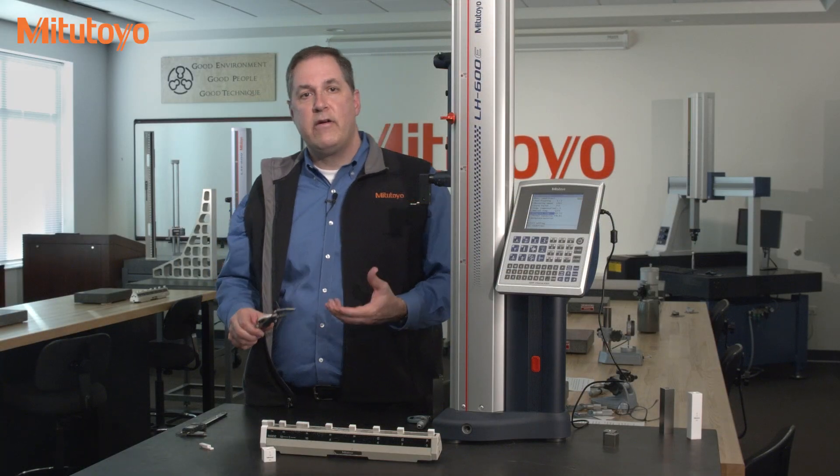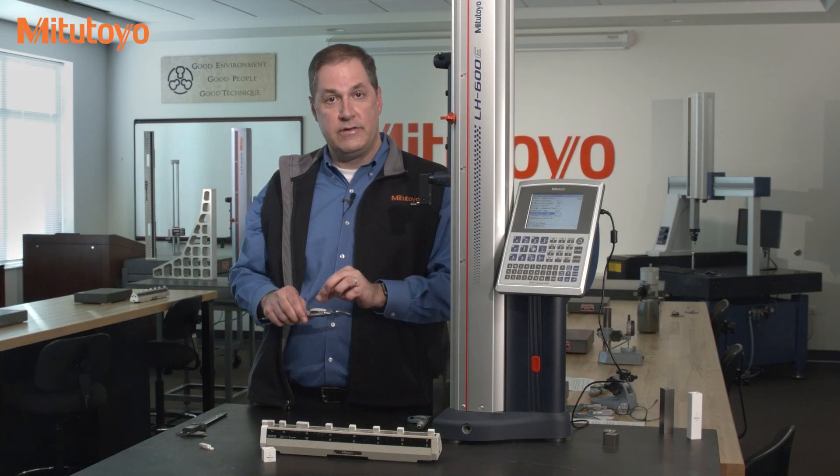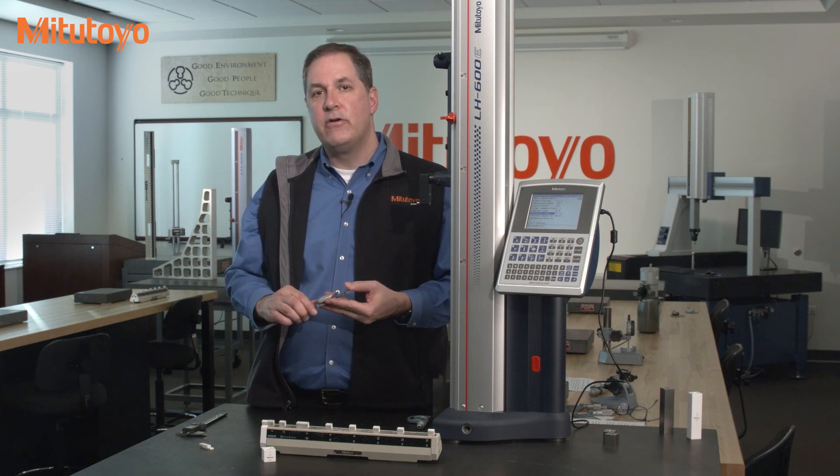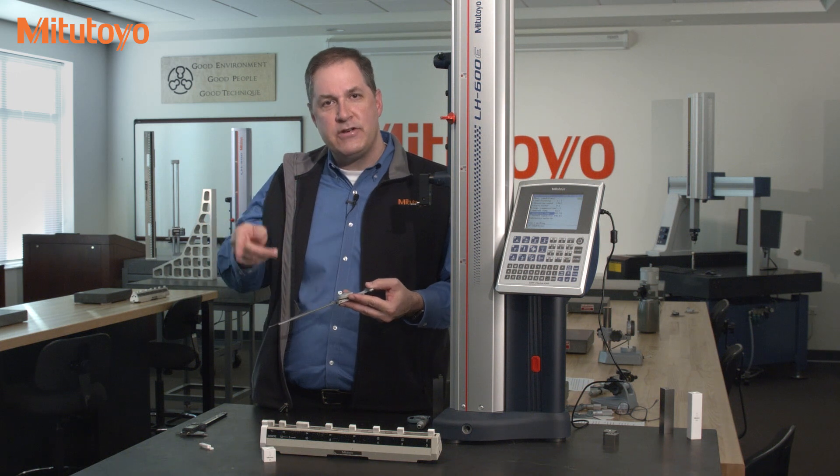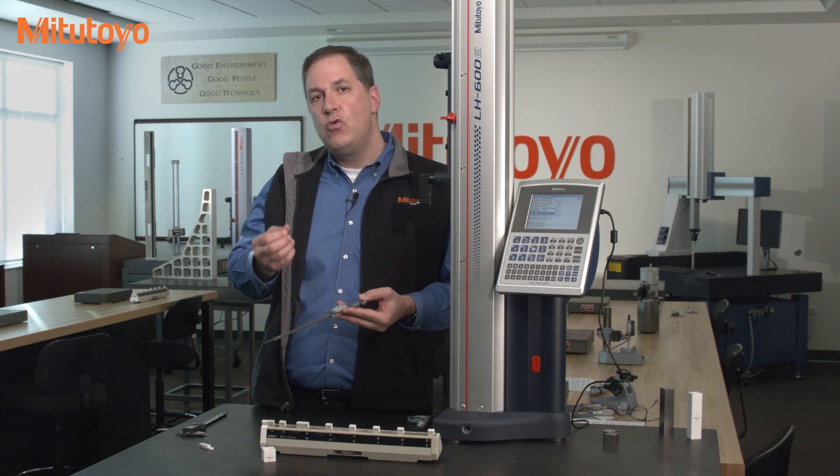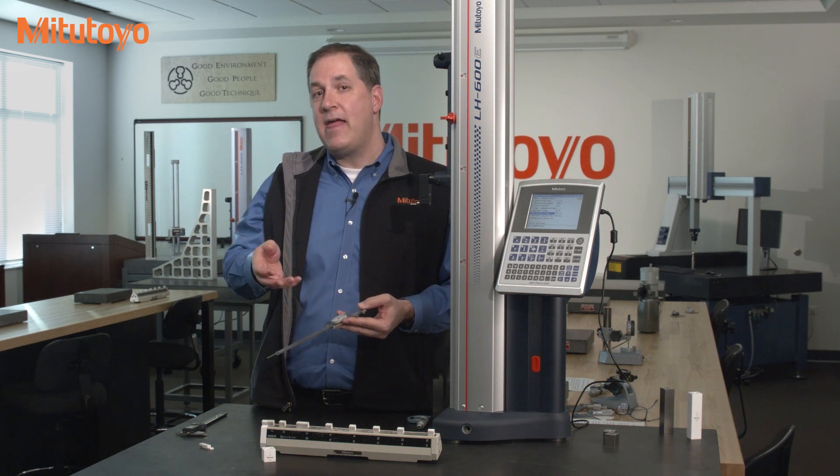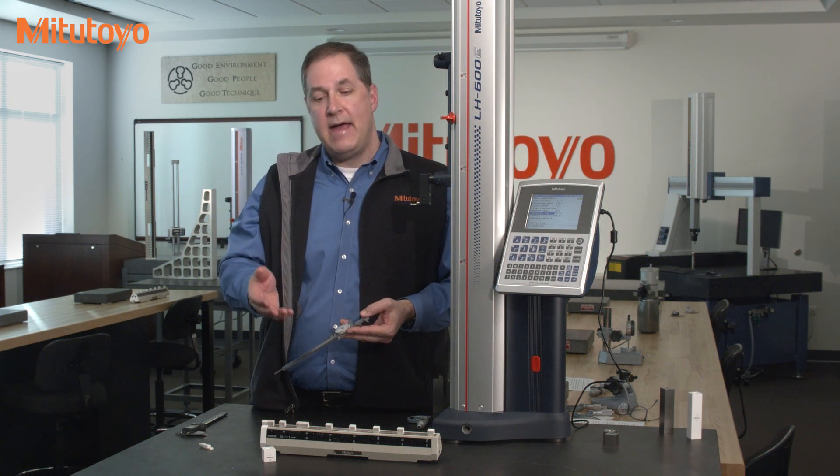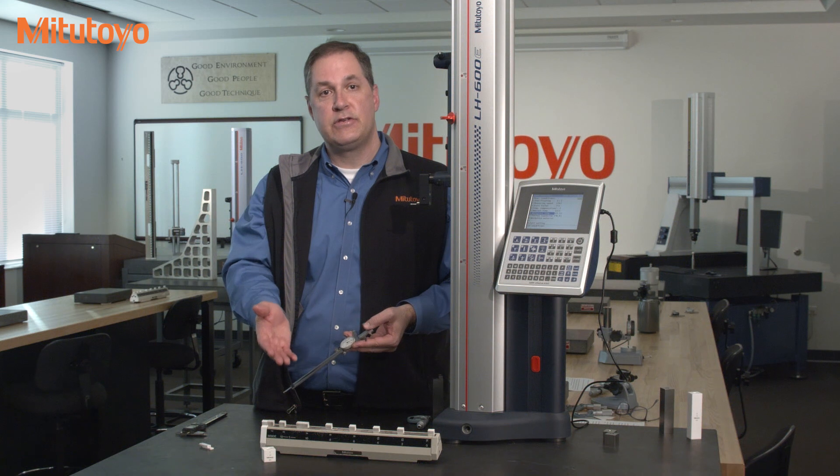Now dial calipers use little gears inside, and the gears can wear. It's possible for there to be errors within a rotation of the dial that you won't see if the calibration method results in the pointer always being at the twelve o'clock position like you just saw.